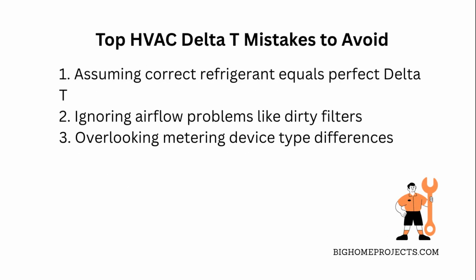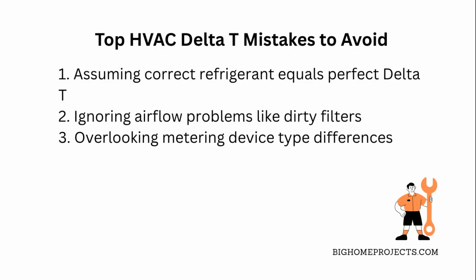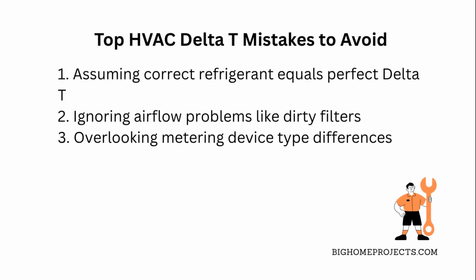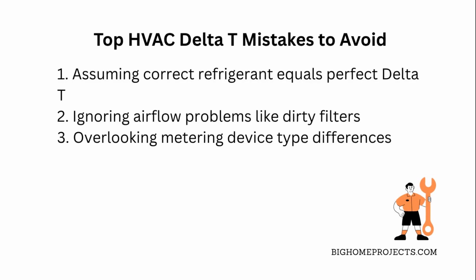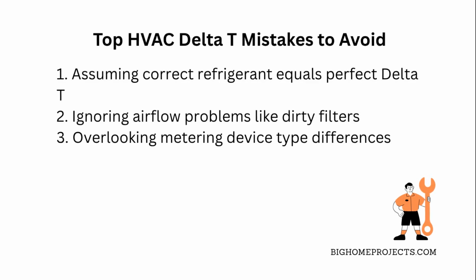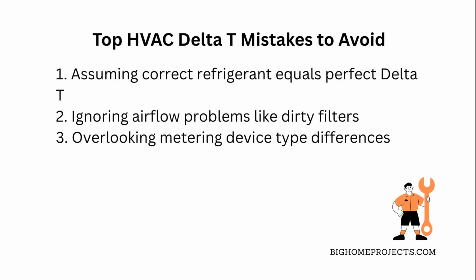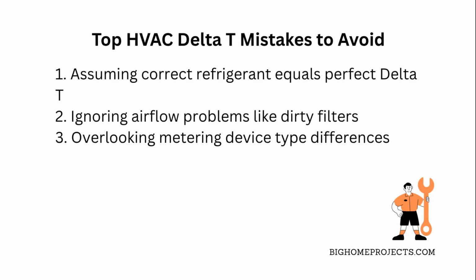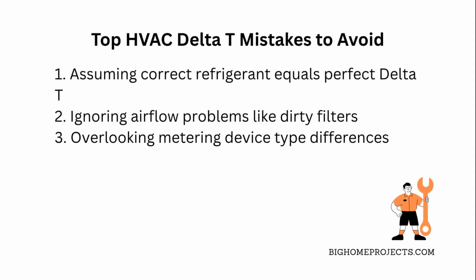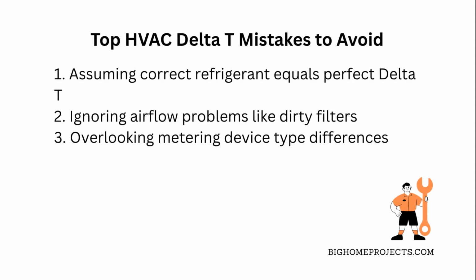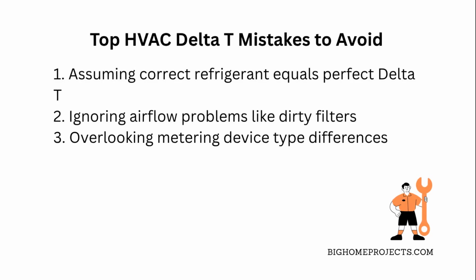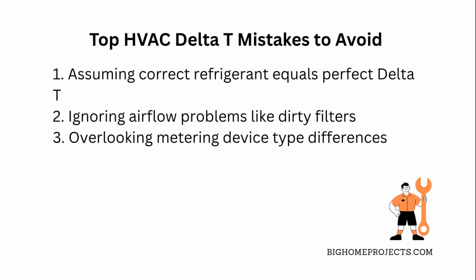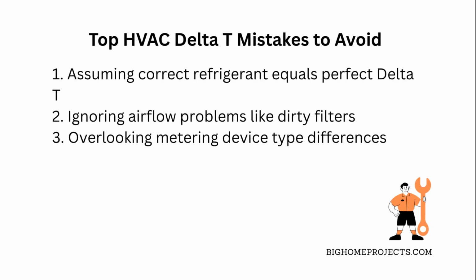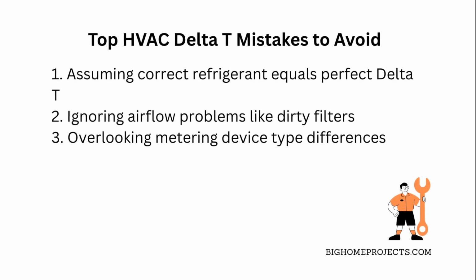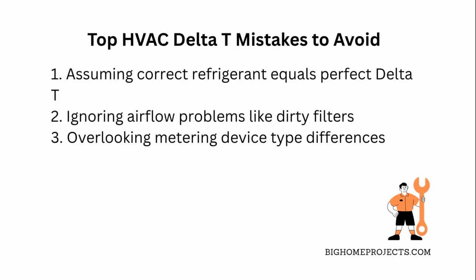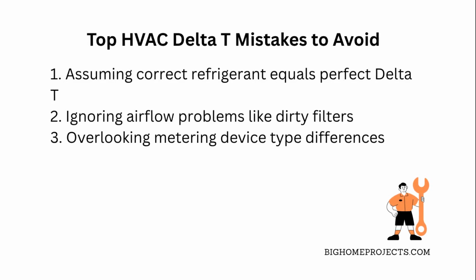One of the biggest mistakes people make when checking HVAC Delta T is assuming a correct refrigerant charge guarantees a perfect temperature difference. Fix that by double-checking humidity levels and making sure your system is suited for your building's heat load. Another common issue is ignoring airflow problems like clogged filters or dirty coils. Cleaning or replacing those can seriously help your Delta T numbers get back on track. Lastly, people often overlook the type of metering device their system uses. Pistons and capillary tubes behave differently than expansion valves, so knowing what you've got can prevent confusion and guide proper troubleshooting.